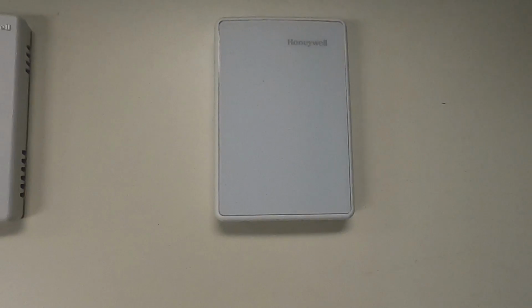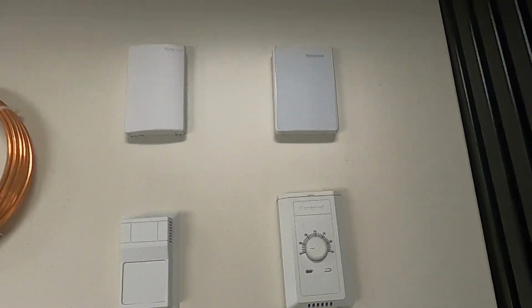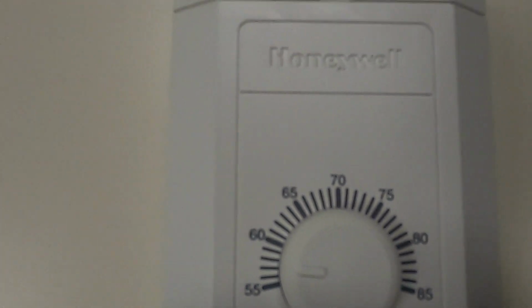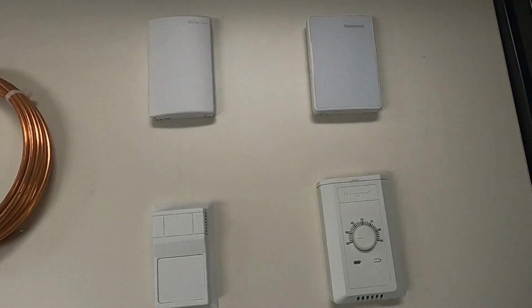To control the air and water circulating with required conditions, we will define the controlling parameters with inputs being received. We will be looking at possible analog inputs in this video. We will see the design criteria to choose appropriate sensors according to the applications. Majorly, analog inputs will record temperature, humidity, pressure, indoor air quality, and flow.